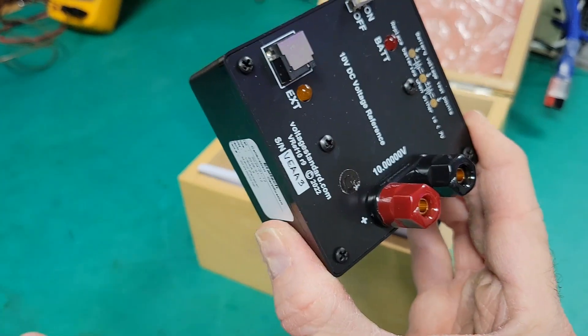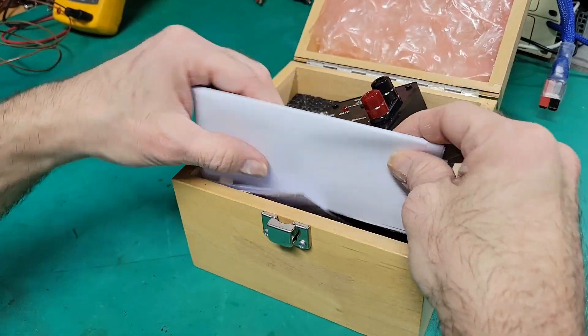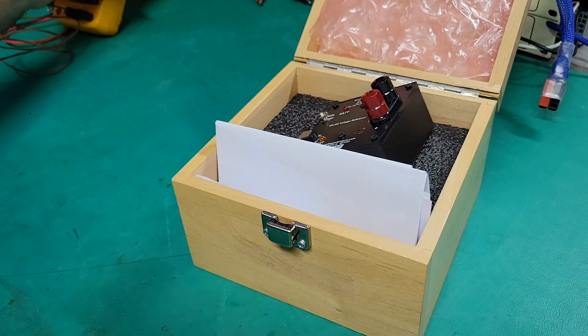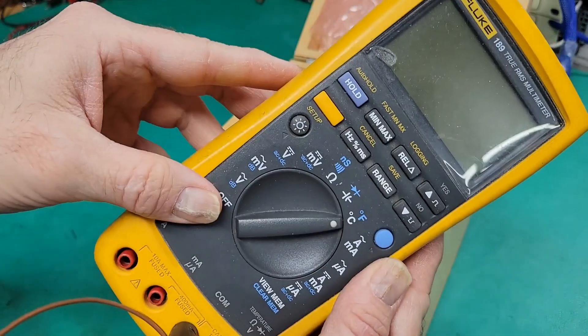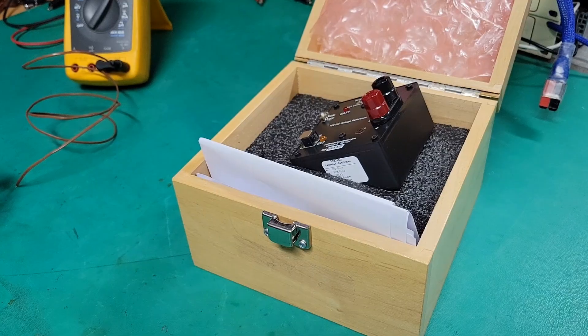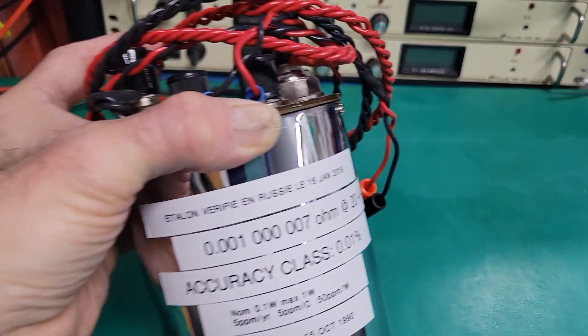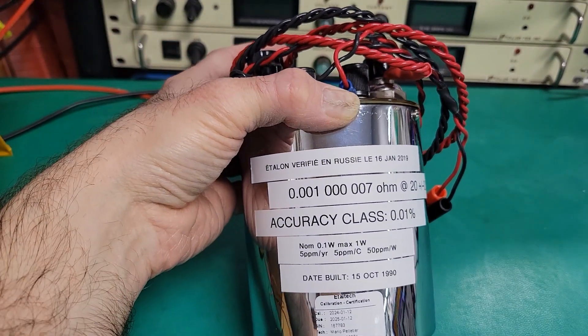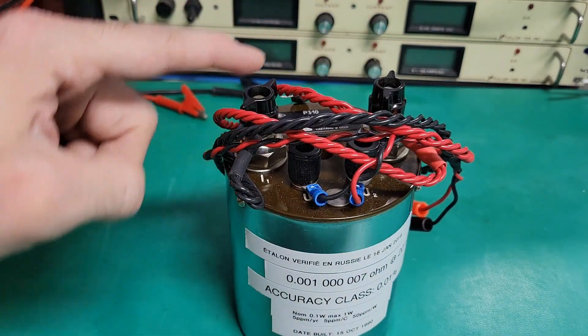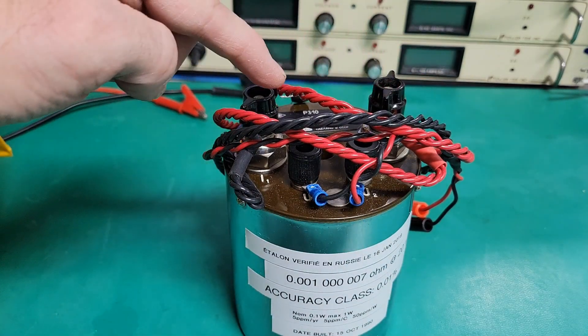With this one and the papers with the temperature compensation and these things, I will be able to check for this multimeter and all the other devices that I've shown you. And if I know that my voltmeter is accurate, I will be able to measure precisely the voltage drop across this precision resistance standard.